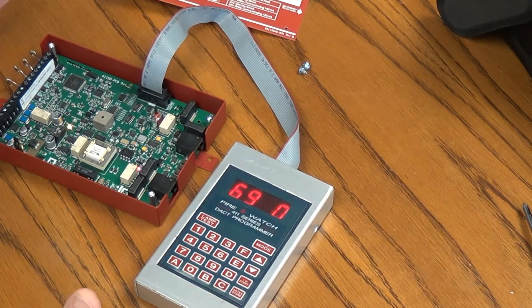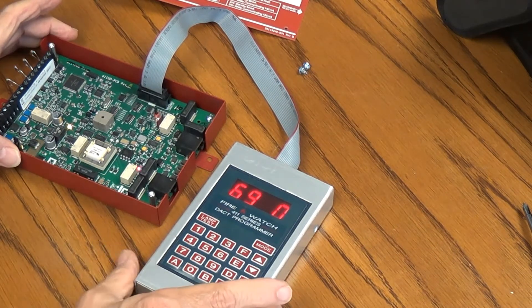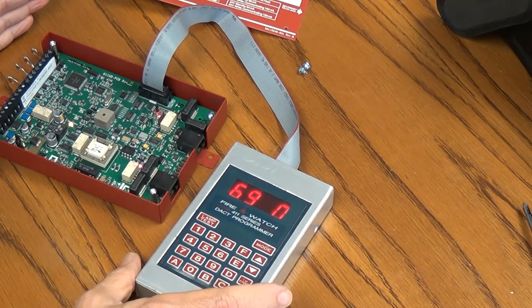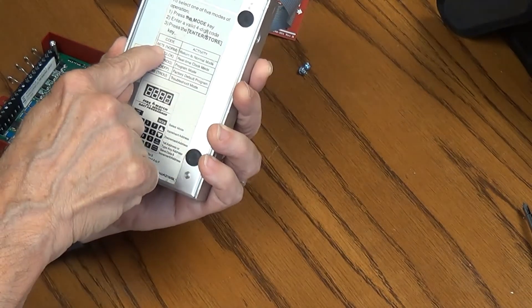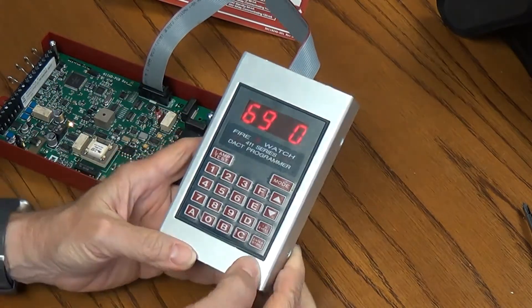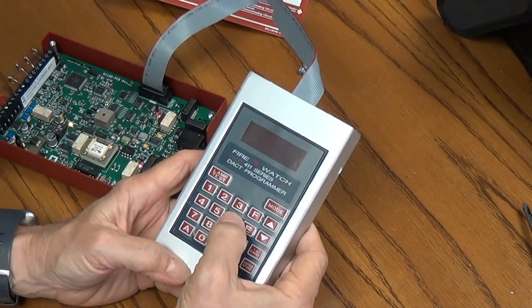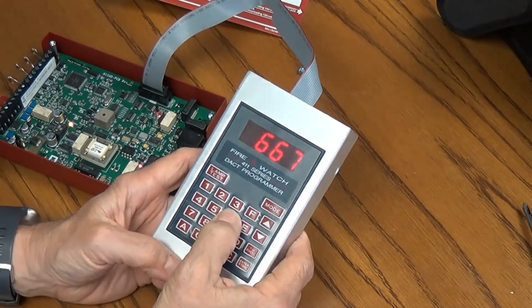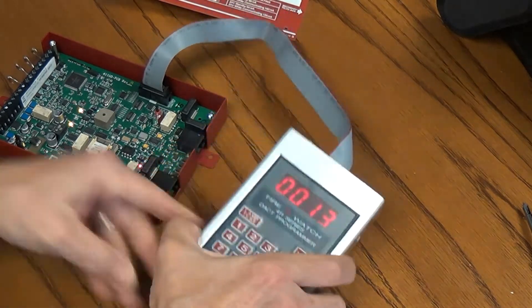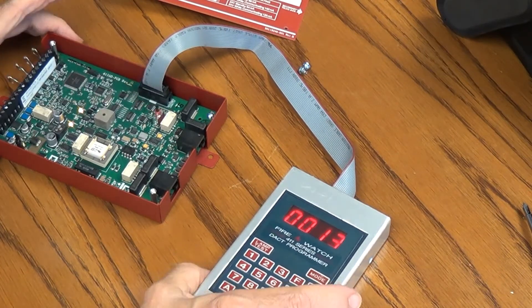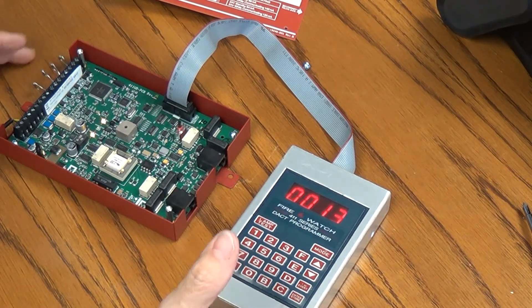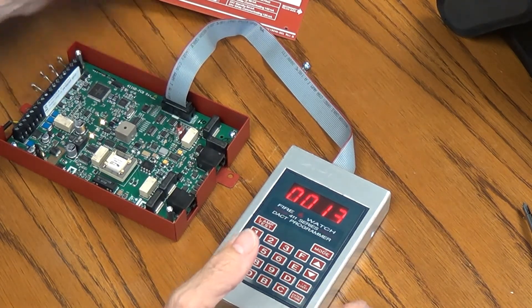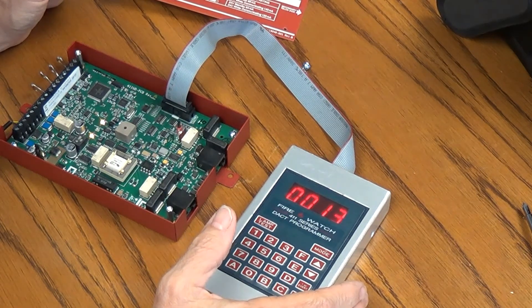Now I am done programming this 411 dialer. So what I'm going to do now is set this back into normal mode. If I look on the back of my programmer, I see norm is 6676. So I'm going to press mode, 6676, and then press enter, silence my alarm, and it is ready to roll. Now I can remove power, unplug it, take my programmer out, button it back up, and I'm ready to take it out to the site.